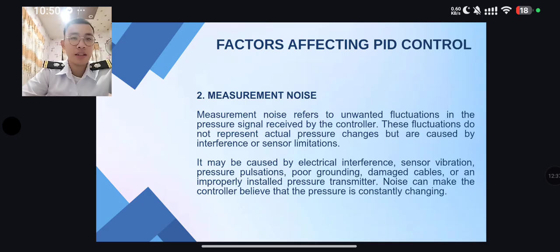Measurement noise consists of unwanted fluctuations in the sensor signal. Because of these pulse signals, the controller may believe the pressure is constantly changing even when the actual process measure is stable. Next are the effects of measurement noise on PID control. Measurement noise reduces the accuracy of the pressure signals received by the controller.